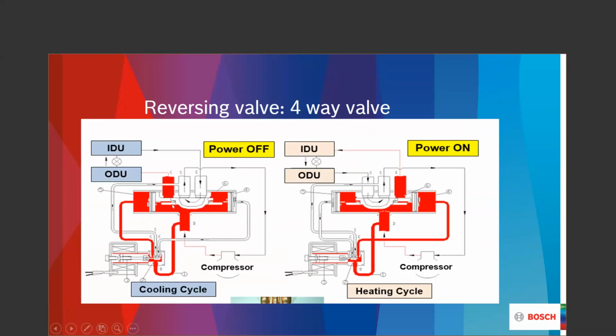And so at that point in time, we literally understand that that 4-way valve up there, two of those lines are going to be basically the same carrier, and one of those is going to be the opposite, high side, low side, if you don't mind, high temperature, low temperature, and the degrees of differential between that particular same pipe. You're probably not looking at a degree and a half or 2 degrees at the most. It's the same tube.